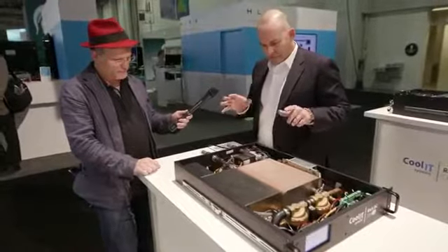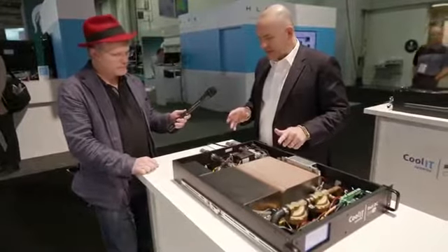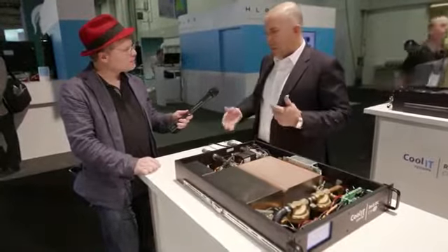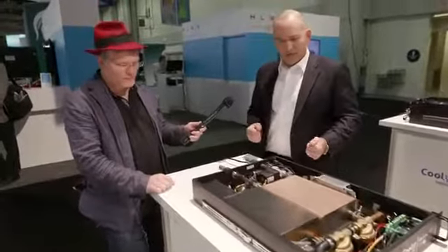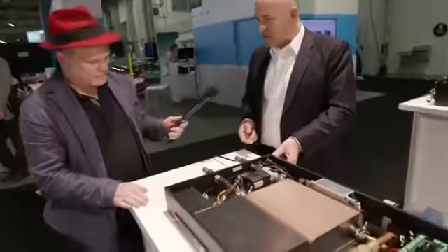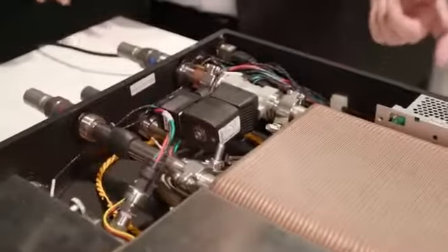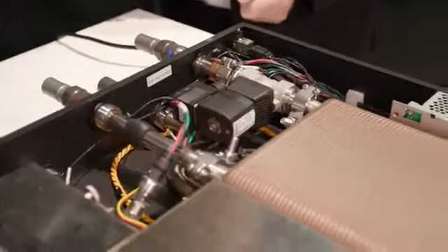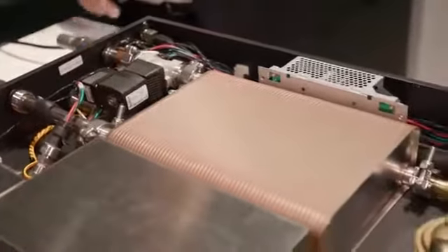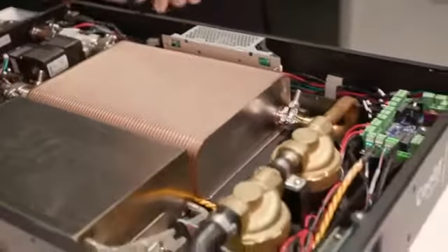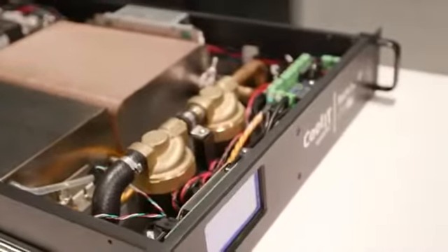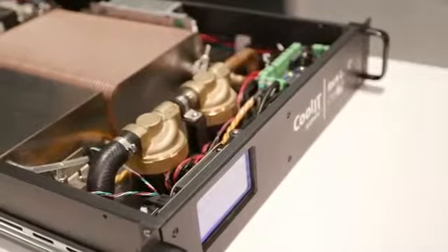The ability for this to dissipate the heat really comes from being water to water, right? So even though it's a very small form factor, it's only 2U, you can do up to 40 kilowatts of heat. Now, we did find that the limitation for this product when you get to higher density racks was flow. We could do about 40 nodes with this, right?